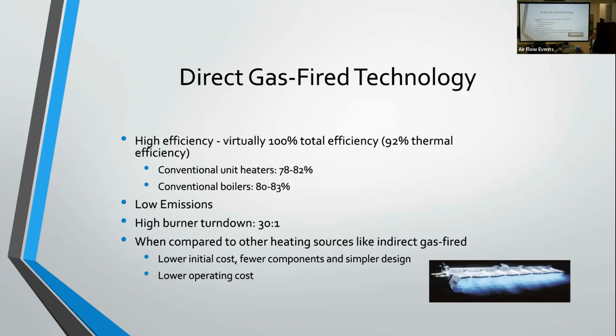And when you compare it to other things like, say, indirect gas fired heat, you've got a lower initial cost because it's a simpler design. There are fewer components. You don't have a large stainless steel heat exchanger and combustion blower with special controls. So it's a simpler setup with fewer components, and obviously a lower operating cost because of the higher efficiencies with direct fire technology.